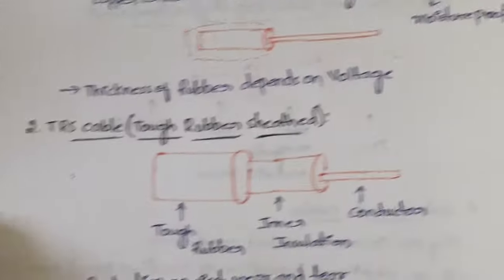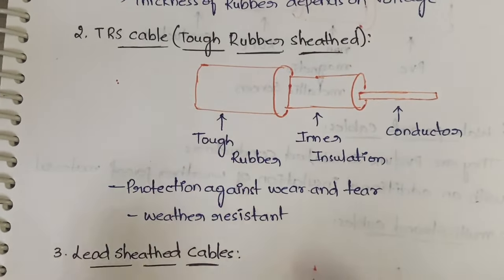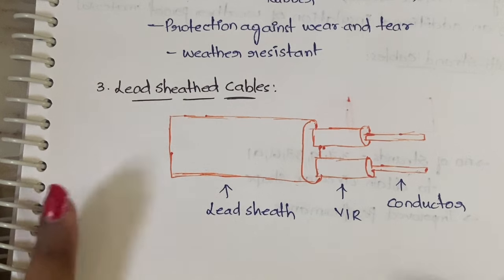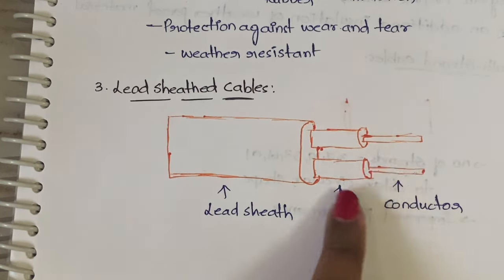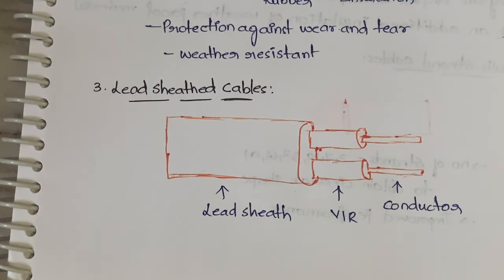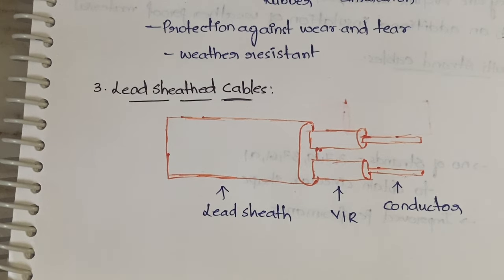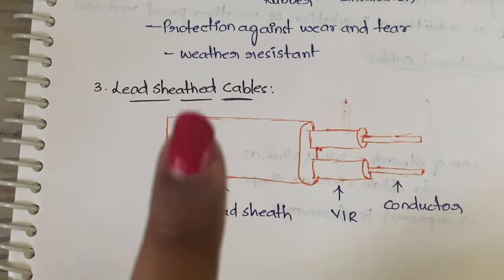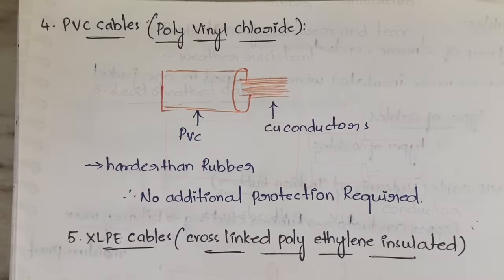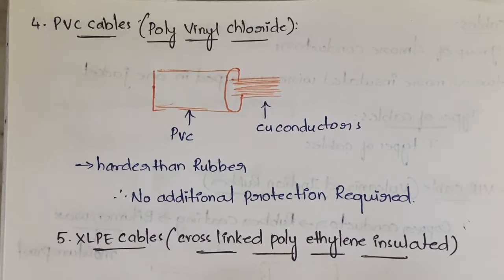The third type is lead sheathed cable. In this cable, the conductors are coated with Vulcanized Indian Rubber, and then all of them together are coated with a lead sheath. This lead sheath protects the cable from moisture and from mechanical injury. Instead of bitumen wax used in VIR cables, lead sheath is used here for that protection.